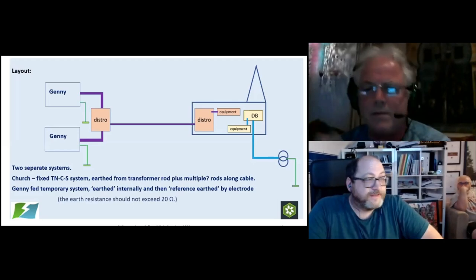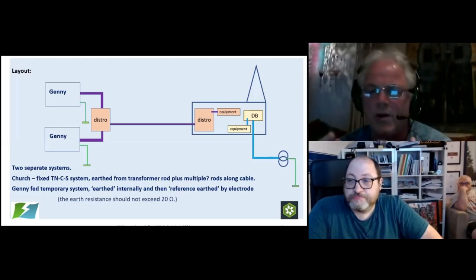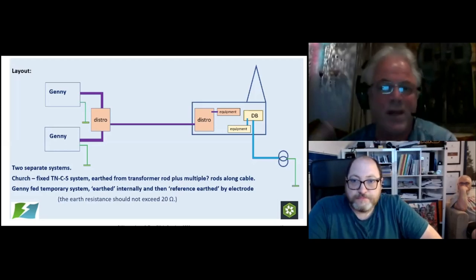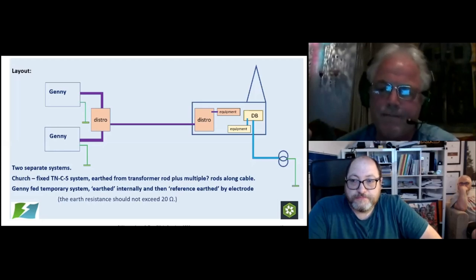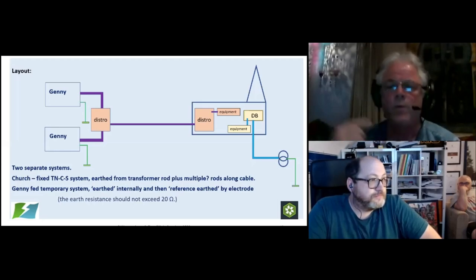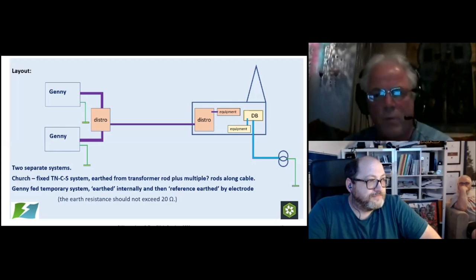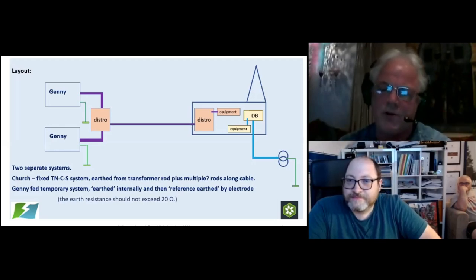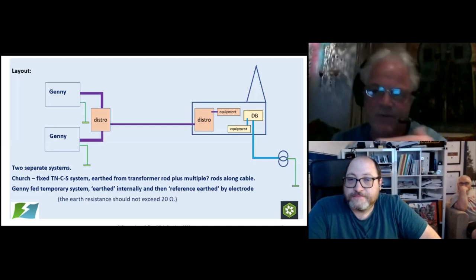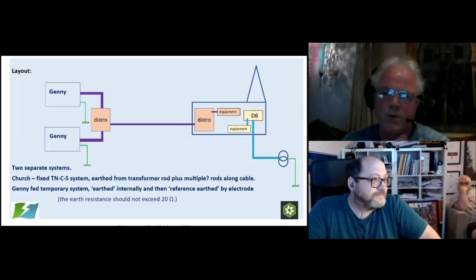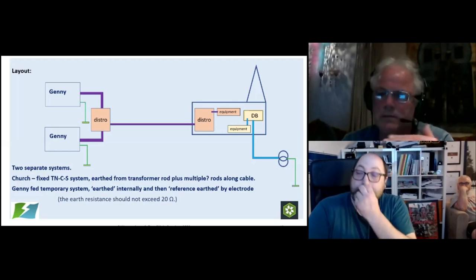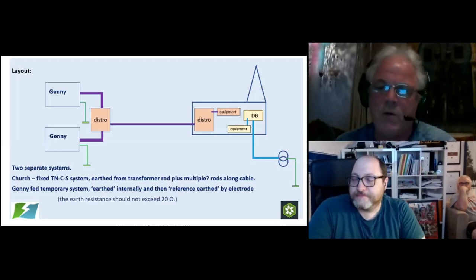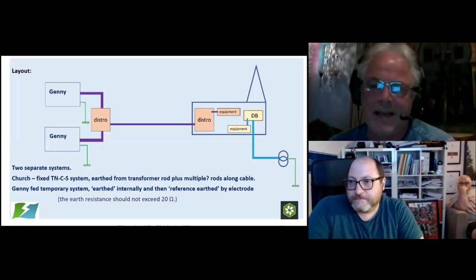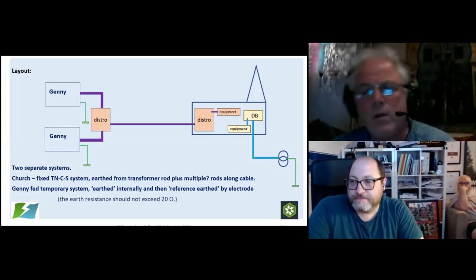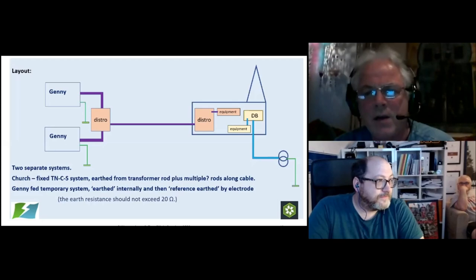But remember, again, we're looking at scenarios where we're looking at multiple faults. And time and time again, we're told in BS 7671, we can only legislate for single fault conditions. So yes, I understand people's thoughts and worries about these things, but we've got to think, hang on, we can legislate for single fault conditions. If we've got multiple faults on multiple systems, then there's very little we can do about those. Otherwise, we'll end up with basically running everything off an isolating transformer individually, because that's the only way of keeping it safe.